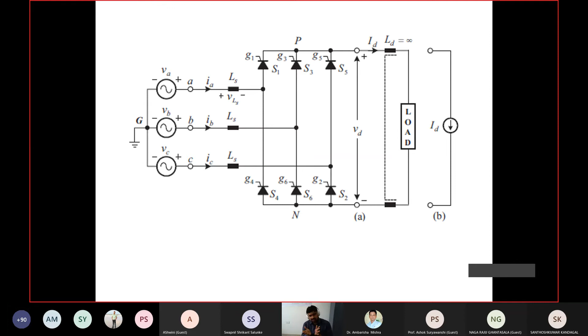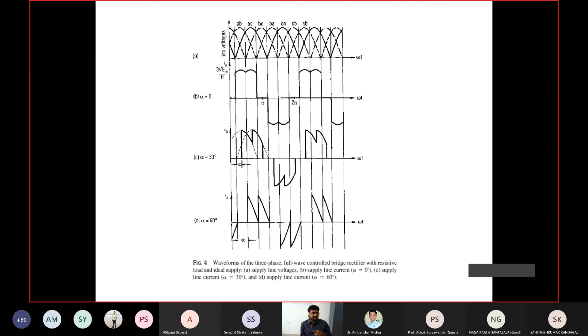What you are seeing on the screen are the source currents drawn from the source based on the firing angle: alpha 0, 30, 60 degrees. You can see how much distortion is happening in the input current waveform of the rectifier, so you can assume how many harmonics are being injected into the grid. Similarly, this is with a pure inductive load, assuming continuous conduction. The input source current is a bit better because it is a quasi square wave.